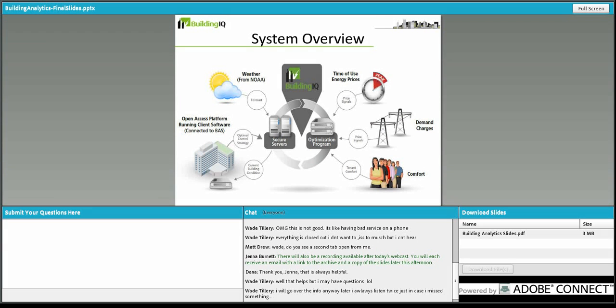In our interpretation of that thinking, we take in a range of information—weather forecast data, time-of-use information, demand response signals, and occupant comfort information. That's all hosted in the cloud with a small on-site component, where we work with devices like Panoptix, or install our own device on site. This gives us access to the site, reading information back from the building, producing an optimized profile, and sending it back to the building.